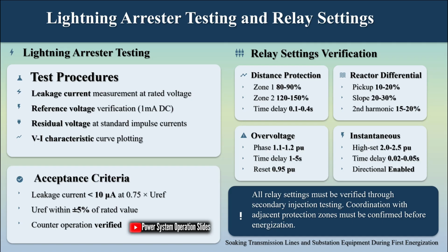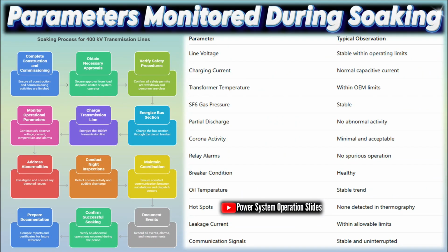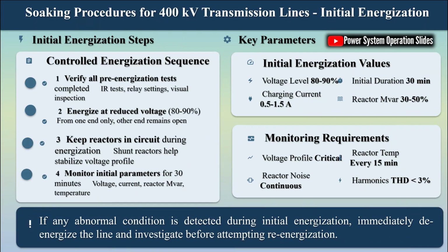Transformer soaking follows a similar principle but is specifically focused on the transformer insulation system and winding assembly. Newly installed transformers often contain residual moisture within insulation materials despite extensive drying and processing during manufacturing. Moisture is one of the most significant factors affecting dielectric strength and insulation life. During low-voltage energization, the transformer insulation system experiences electrical stress that helps reveal weaknesses while allowing the insulation to stabilize.